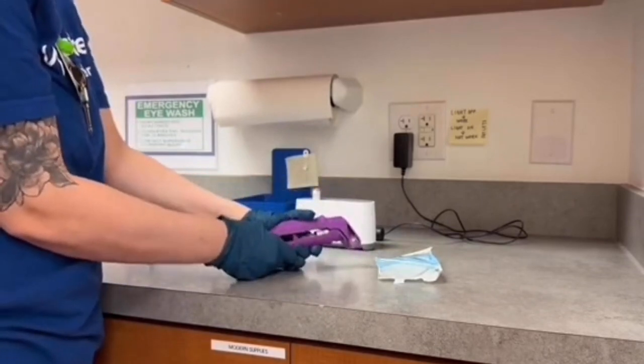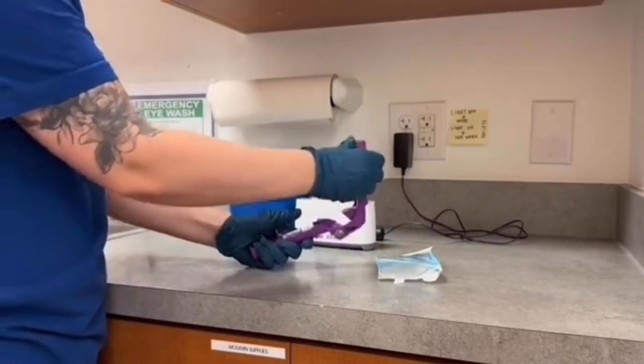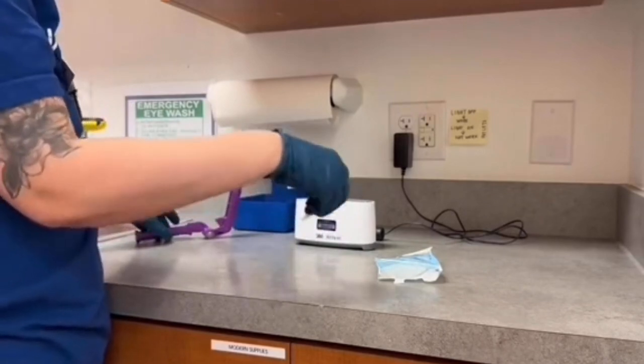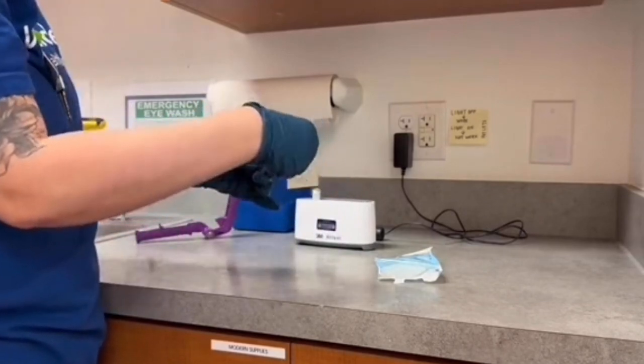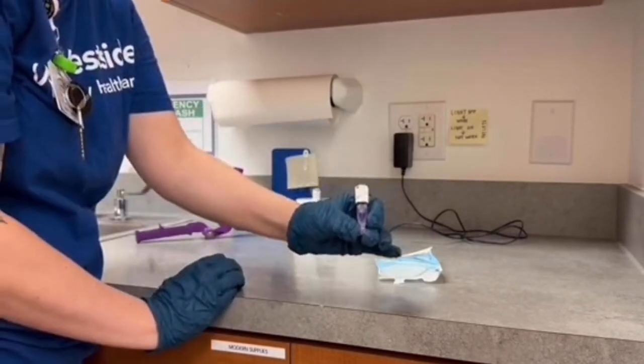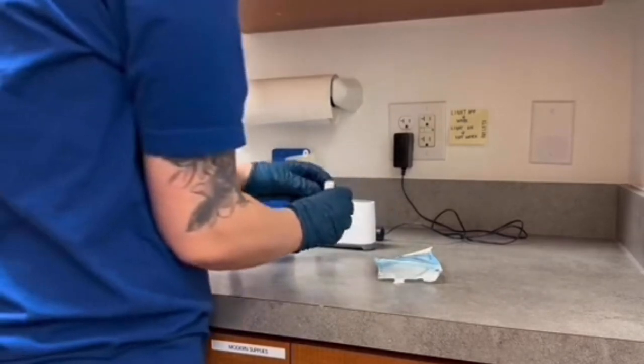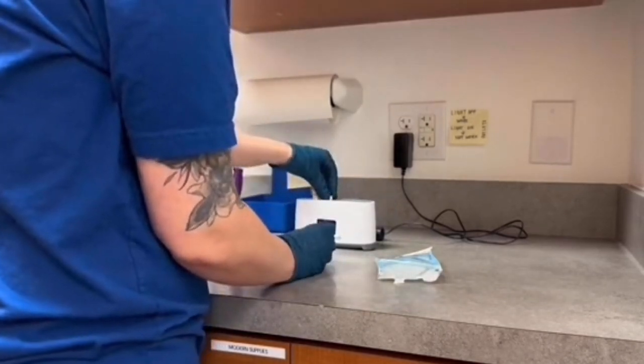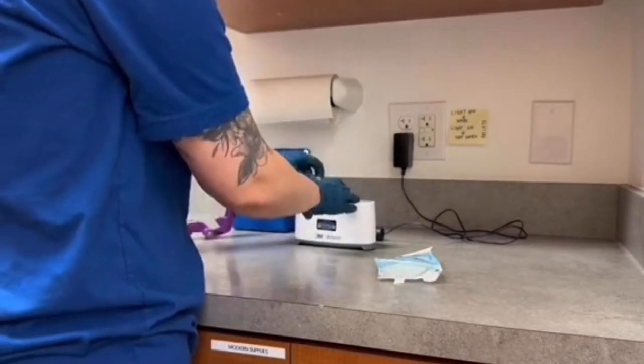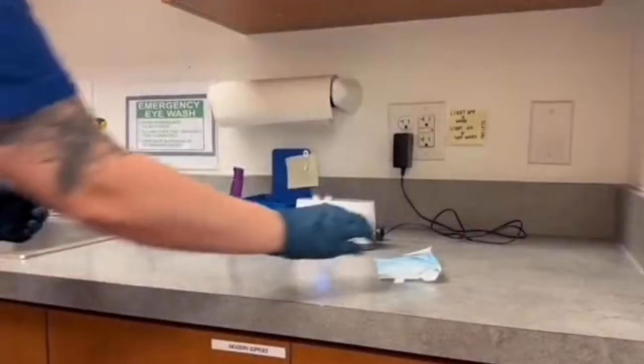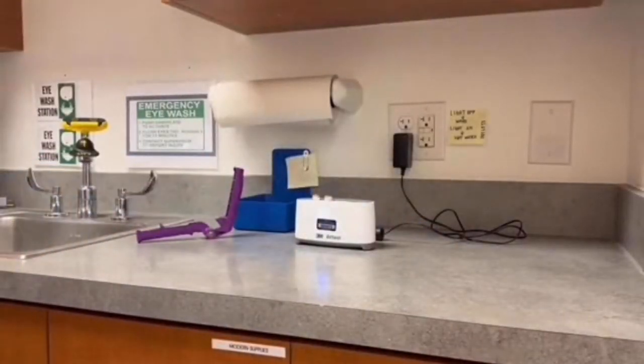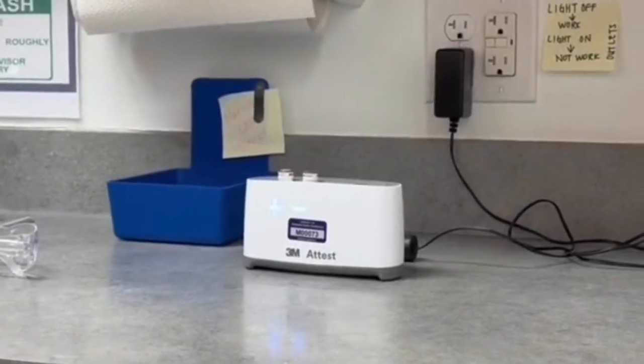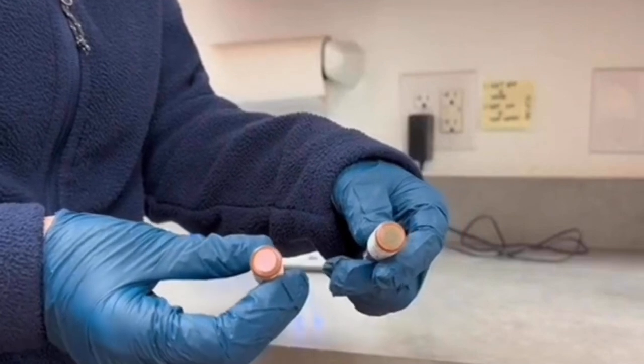Then, after allowing the sterilized BI to cool for at least 10 minutes, you can activate it with the activator and place it in another chamber of the Attest machine. This is the test BI, and since it has been sterilized, the result should always be negative. Also make sure the sterilized BI top changed to the correct color. If neither result is as expected, treat all instruments in that load as non-sterile and repackage and re-sterilize along with a new process challenge device.